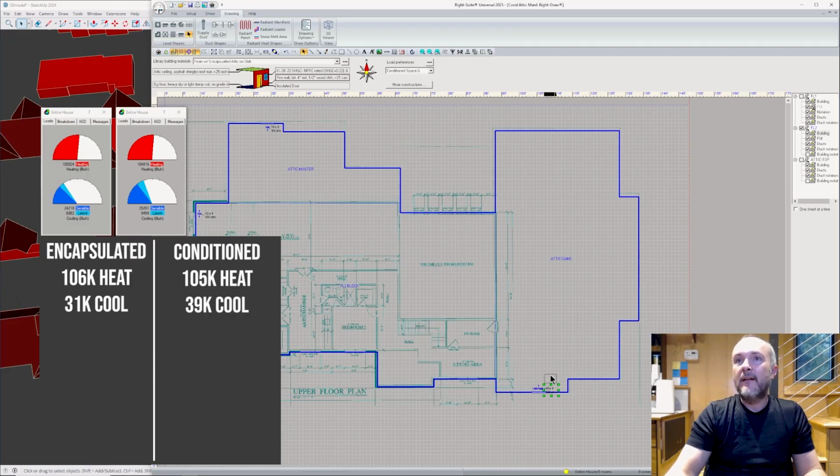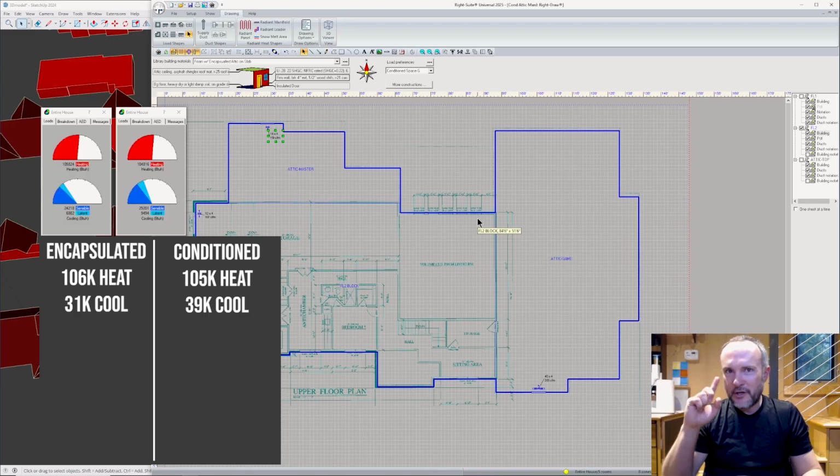And by the way, notice that I'm giving 350 CFM now to this attic game room, 119 to this attic master. These are big room flows. I mean, they're big rooms, let's be honest. Okay, so now we've added the windows. That's just a big question mark. If you're seeing those kinds of plans coming from architects and you're not designing it this way, then you don't really know what it's going to do to it.